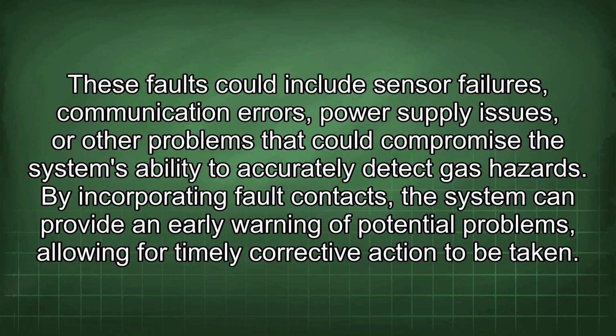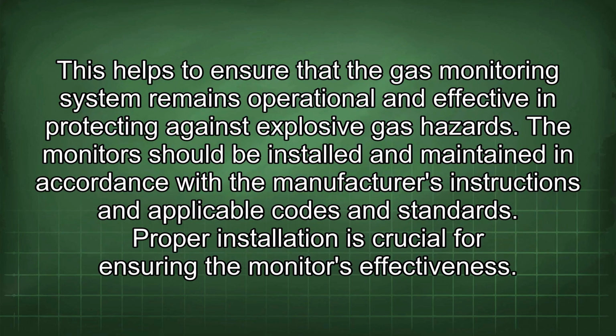By incorporating fault contacts, the system can provide an early warning of potential problems, allowing for timely corrective action to be taken. This helps to ensure that the gas monitoring system remains operational and effective in protecting against explosive gas hazards. The monitor should be installed and maintained in accordance with the manufacturer's instructions and applicable codes and standards. Proper installation is crucial for ensuring the monitor's effectiveness.